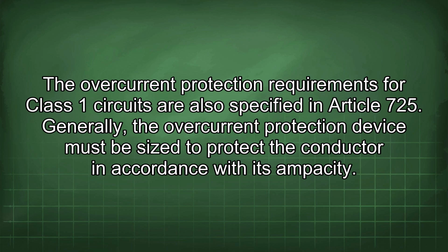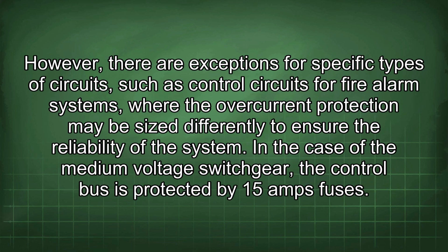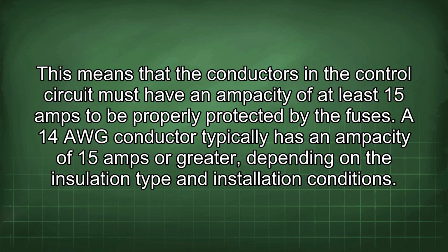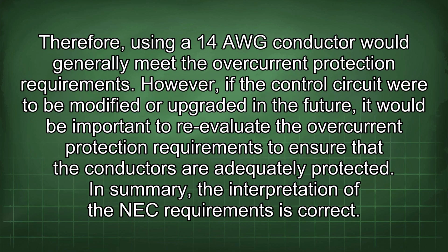The overcurrent protection requirements for Class 1 circuits are also specified in Article 725. Generally, the overcurrent protection device must be sized to protect the conductor in accordance with its ampacity. However, there are exceptions for specific types of circuits, such as control circuits for fire alarm systems, where the overcurrent protection may be sized differently to ensure the reliability of the system. In the case of the medium voltage switchgear, the control bus is protected by 15 amps fuses. This means that the conductors in the control circuit must have an ampacity of at least 15 amps to be properly protected by the fuses. A 14 AWG conductor typically has an ampacity of 15 amps or greater, depending on the insulation type and installation conditions. Therefore, using a 14 AWG conductor would generally meet the overcurrent protection requirements.